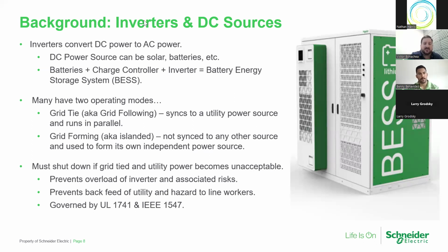A lot of modern inverters have the ability to switch between these two operating modes, and that's where some of the complexity about using inverters for backup power comes into play. One rule around grid tie inverters is that if you're running in grid tie mode and power becomes unacceptable, be that under frequency, under voltage, or any other parameter like unbalance, the inverter must shut itself down. It's a safety feature, defined and called out in UL 1741 and IEEE 1547, which are some of the standards around microgrids and inverters.